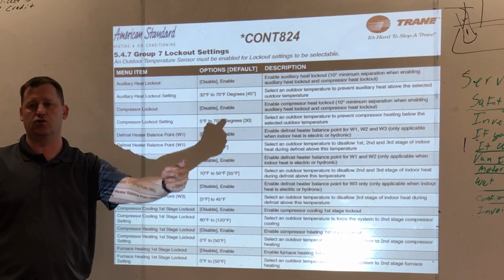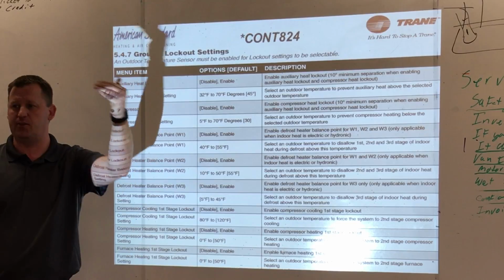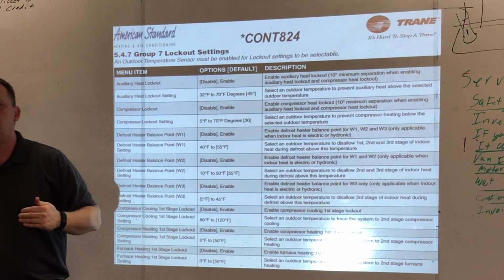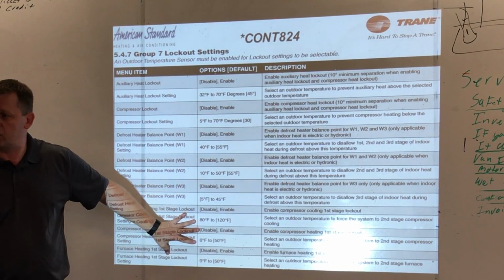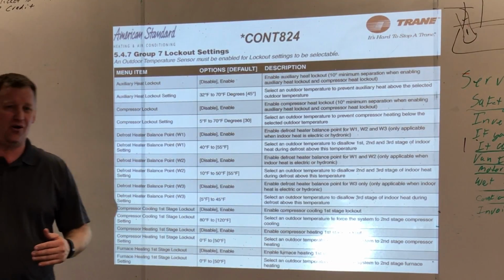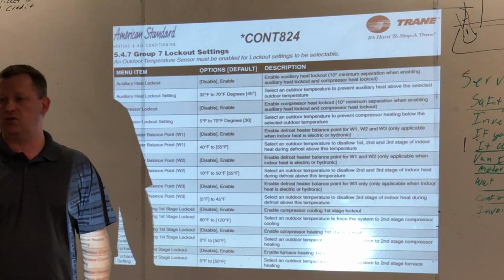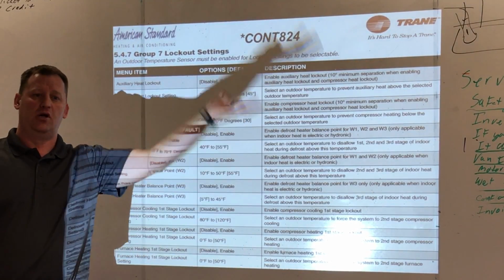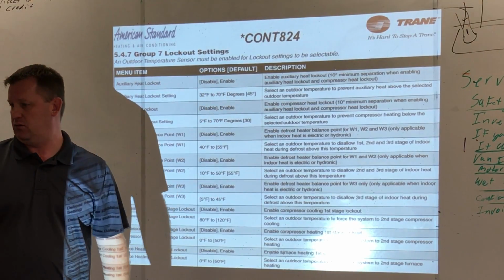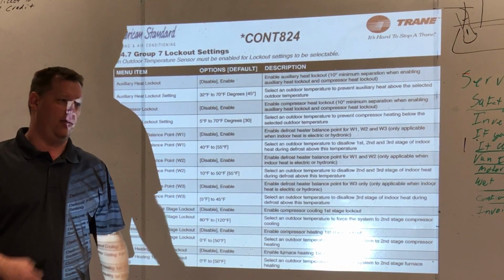So why even run first stage, to create a 10-minute time delay to lose more temp in the house? These are mostly for fixing those issues where the homeowner says, it drops 2 degrees in my house at 100 degrees outside before the unit starts recovering. Okay? We can fix those issues, and that's how it is.